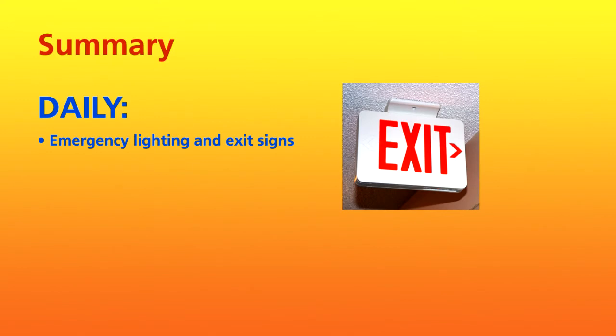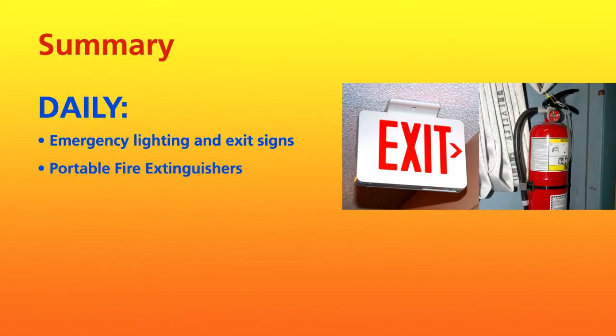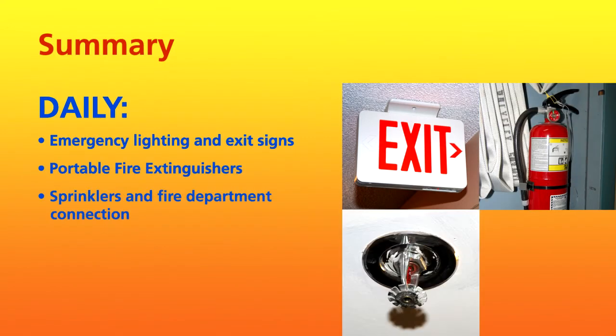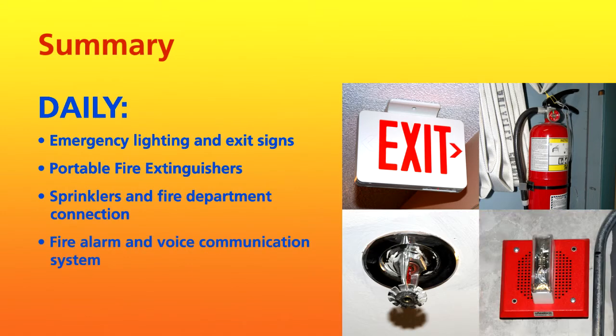We've covered the many tasks associated with good preventive maintenance for fire protection and life safety systems in your building. Now let's summarize what we've learned. On a daily basis, staff must make a visual check for damage, obstructions, or trouble indicators on emergency lighting and exit signs, portable fire extinguishers, sprinkler heads, pipes, and fire department connection, and fire alarm and voice communication systems, including main control panel and pull stations.